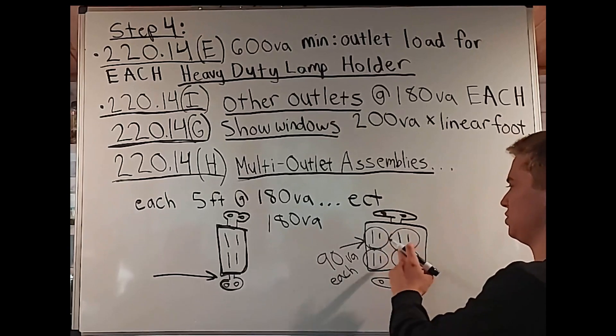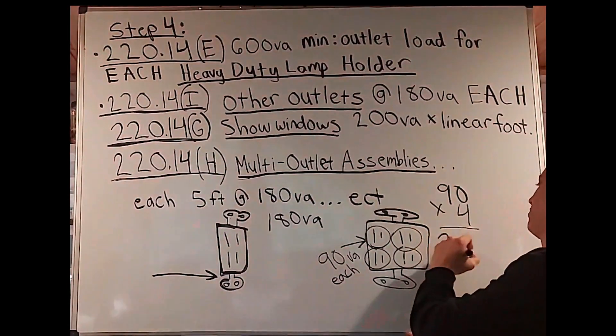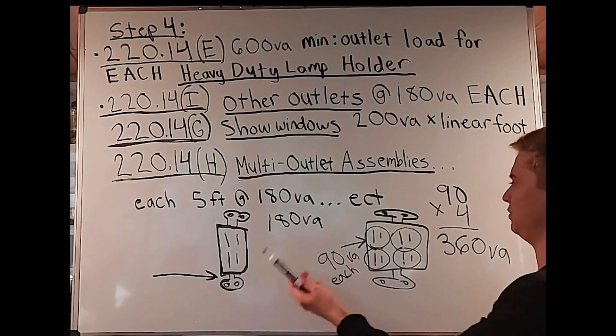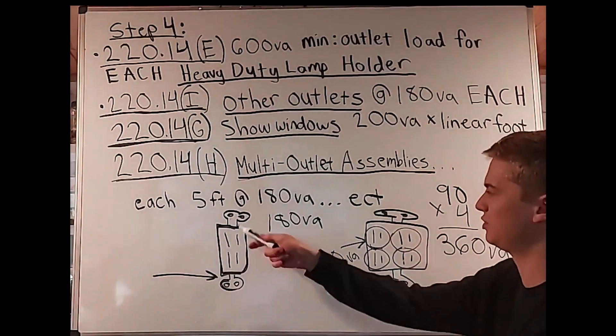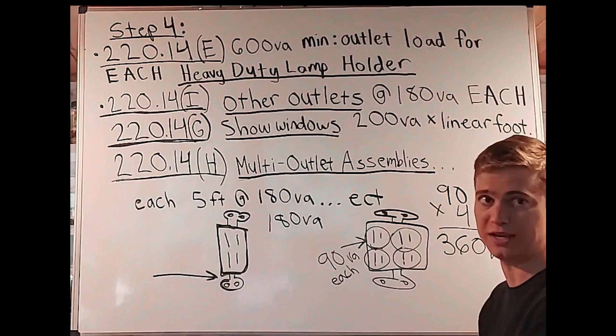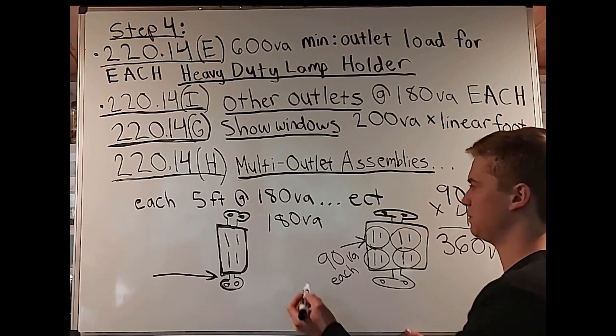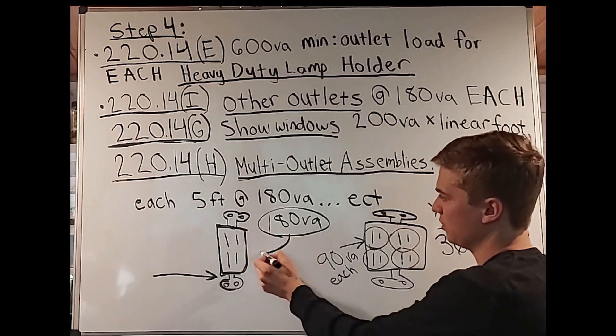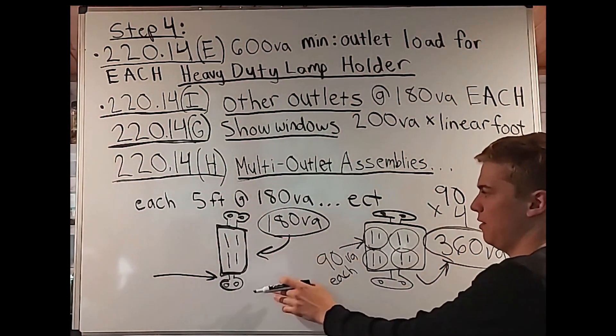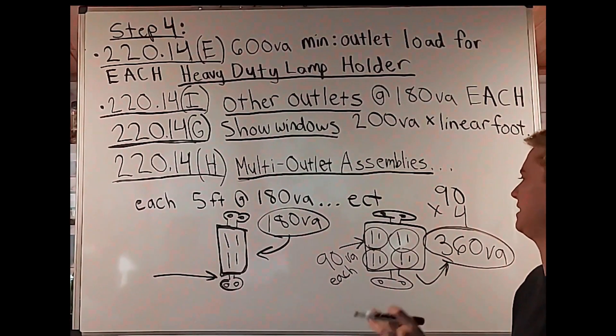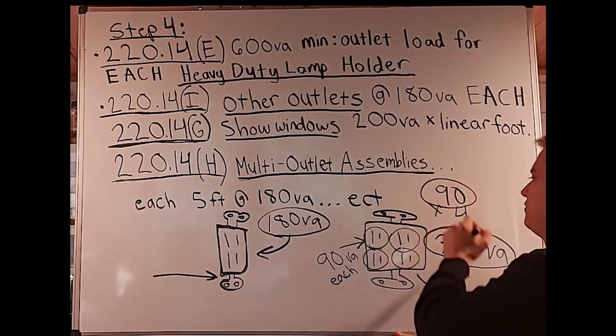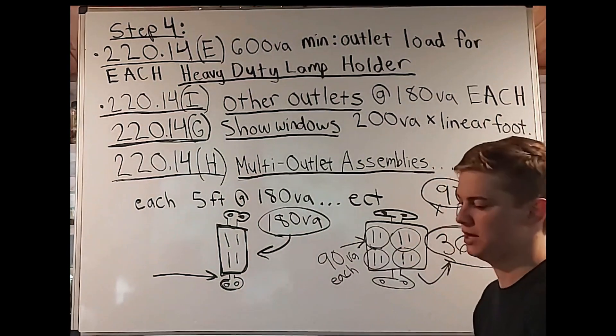If you have more than four receptacles, you continue adding 90 volt amps per each additional one. That logically makes sense and it's good when the codebook makes logical sense. Two receptacles at 180 VA and four receptacles at 360 VA have the same per-outlet rating, so the system scales consistently. If you go beyond four, just keep adding 90 VA per receptacle.